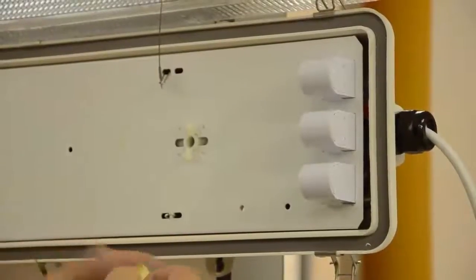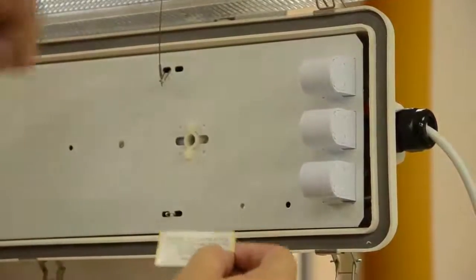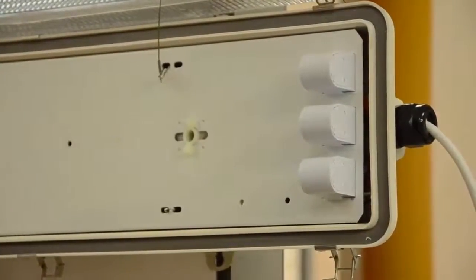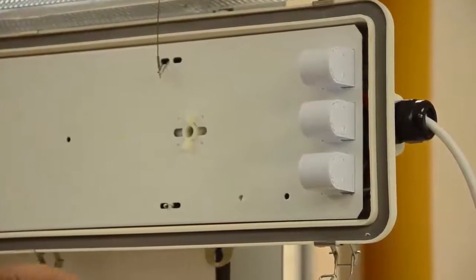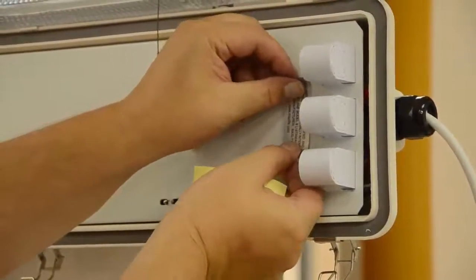Now before we put in our LED T8 lamps, I'm going to apply this label. This label is going to warn the next guy down the road 15, 20 years from now that when he does maintenance on this fixture, that there is direct line voltage on these sockets.